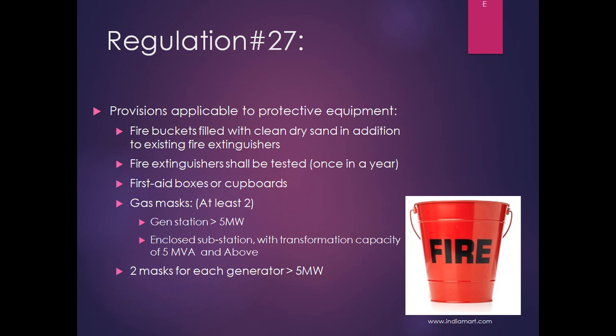Regulation 27 talks about provisions applicable to protective equipment. Fire buckets filled with clean dry sand in addition to the existing fire extinguishers. If you see industry today, everybody uses passive fire protection systems and active fire protection systems, like carbon dioxide systems, somebody uses nitrogen emulsifier systems. Even though you have a very good active fire protection system, somebody also uses portable fire extinguishers. So this regulation is saying that even if you have all those things in their place, you must have some fire buckets filled with dry sand, because there may be cases when these systems may not perform their intended function at the proper time.